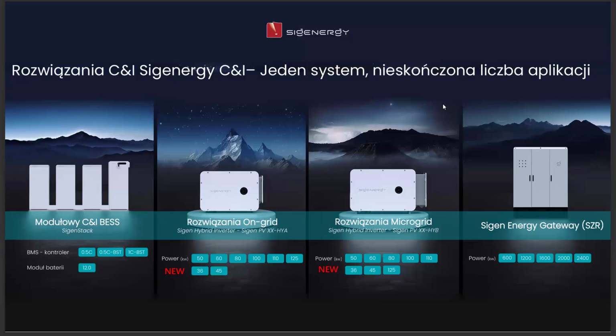3. Power regulation and generator protection. We do not fight the generator, we adapt to it. In the app, we enter the generator's rated power and maximum allowable load, and Sigen ensures it is not overloaded by dynamically supplying the missing power from storage. 4. Free fuel function, manual charging from generator. A very practical question often comes up. What if the customer has access to cheap or free fuel and wants to charge the battery from the generator at a chosen time? In the MySigen app, the user has full control.